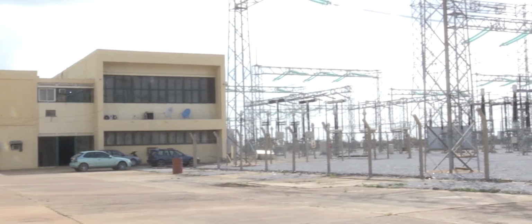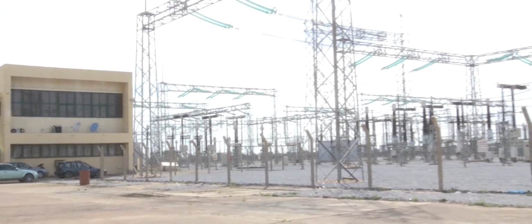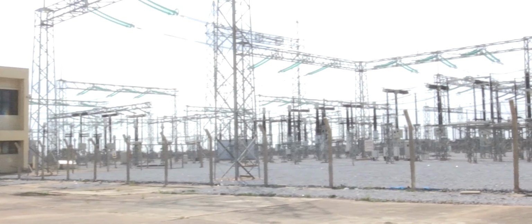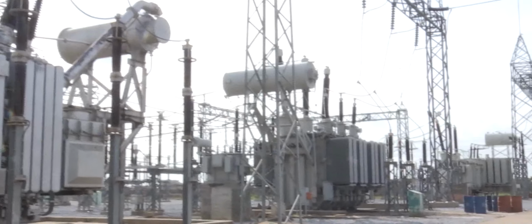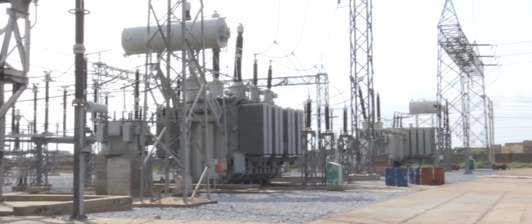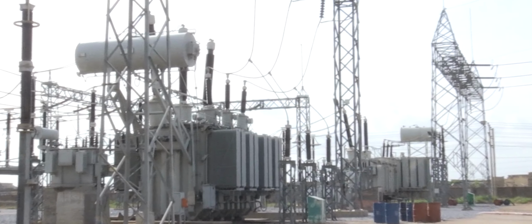For projects taken up by contractors, here at Kumbotso we recently received contractors from the World Bank, the Chinese. They will upgrade one of the 4 by 150 MVA transformers, replacing it with a 300/375 MVA transformer - ONAF, meaning Oil Natural, Air Forced - which will replace one of the 150 MVA transformers.